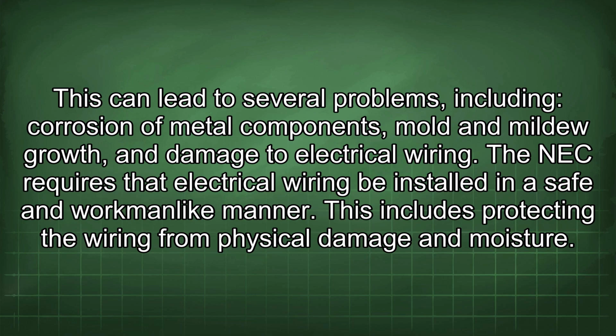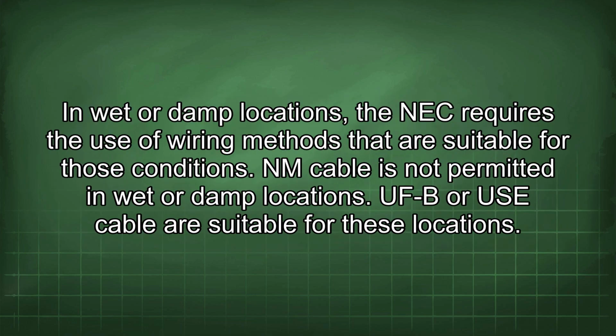The NEC requires that electrical wiring be installed in a safe and workmanlike manner. This includes protecting the wiring from physical damage and moisture. In wet or damp locations, the NEC requires the use of wiring methods that are suitable for those conditions. NM cable is not permitted in wet or damp locations. UF or USE cable are suitable for these locations.